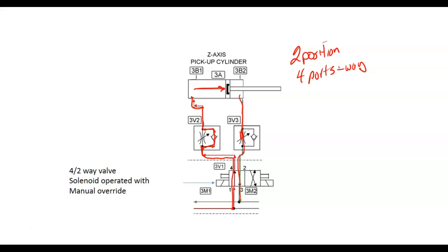But that's not the way the thing goes. So what they do is they start off with the number of ports, let's say a 4, the number of positions, 2, and then they say way, which is totally wrong, but that's the industry standard. So we'd call this a 4-2-way valve. And that's the way you'd order it. But it's 2 position, 4 ways. Notice the power and the exhaust are always what? Odd numbers. And then the working ports are always even. Pretty good. That's the way I've seen it on pneumatics. Some of the hydraulic valves, instead of 1 and 3, they'll label it P and T. So P would be pressure and T would be tank, and then the other ports would be 4 and 2. But you'll see that done a lot.